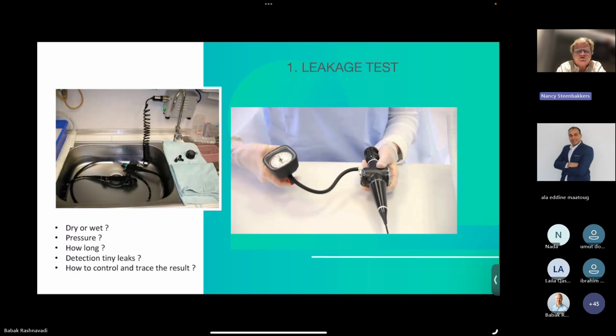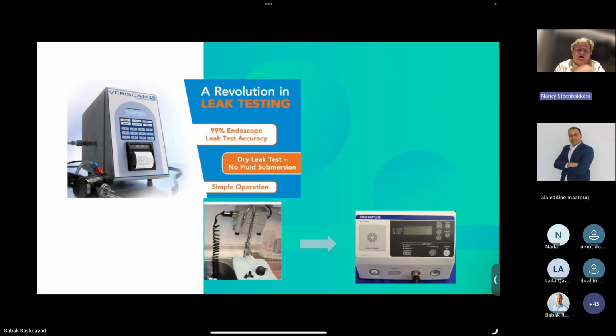So the thing is, you have to ask yourself, are we performing the leak test now, dry or wet? What is the pressure that we are respecting? How long are we performing the leak test? Are we detecting the tiny leakages? And how are we controlling and tracing the results? Next, please. So these are all kinds of leak testers in the market, and they also announce that you have to perform the leak test in a dry condition. Next, please.